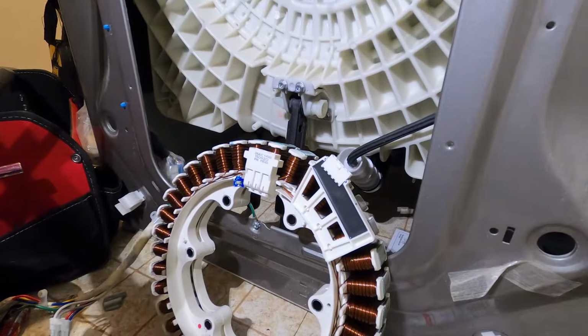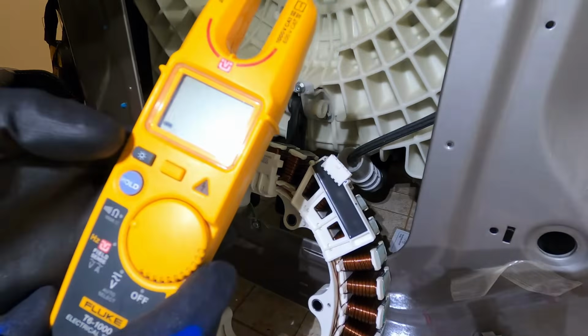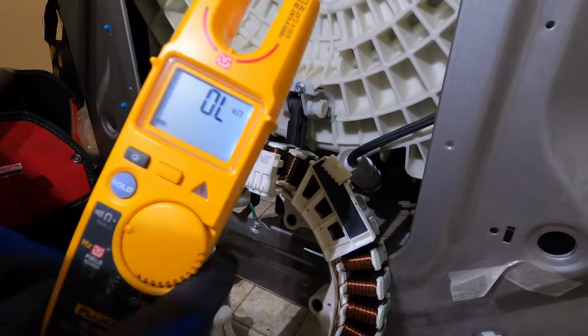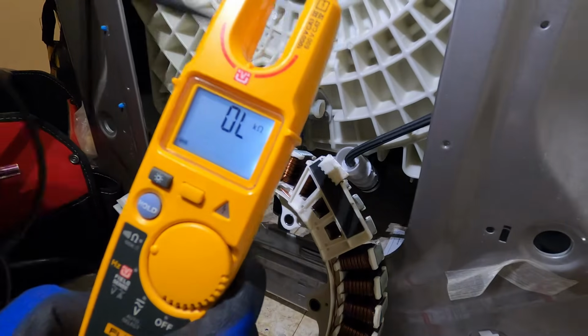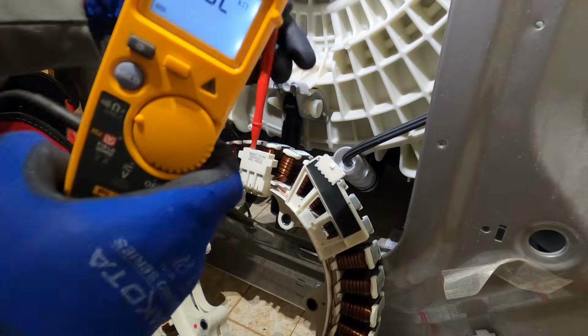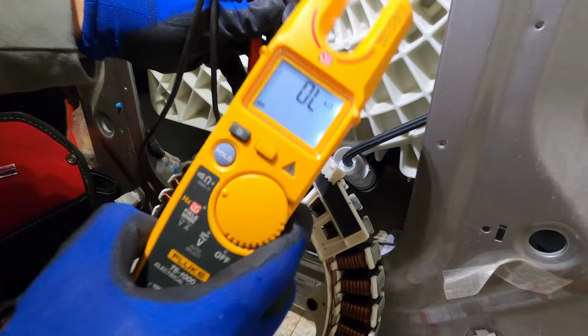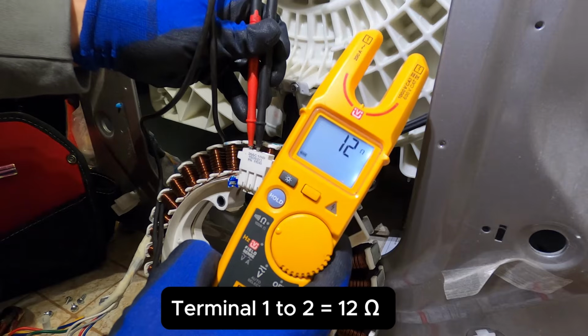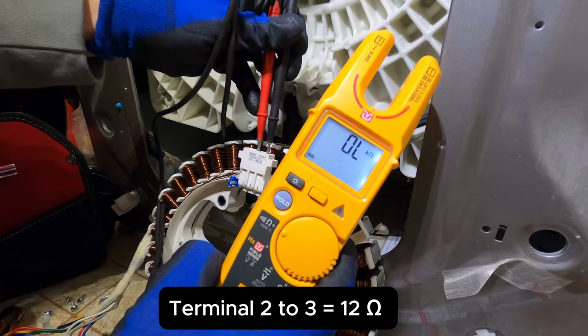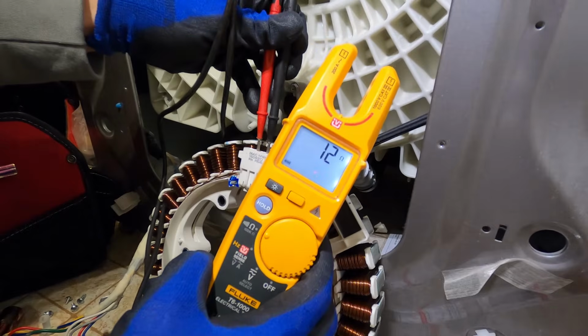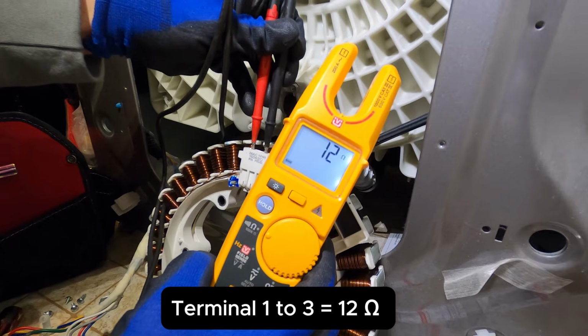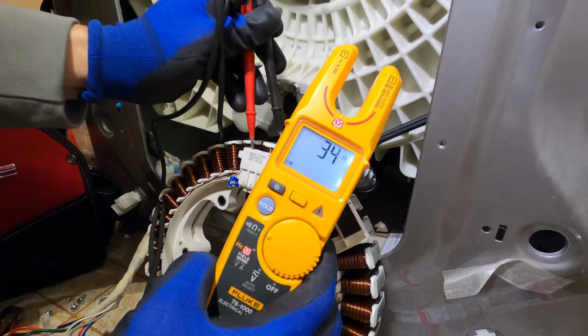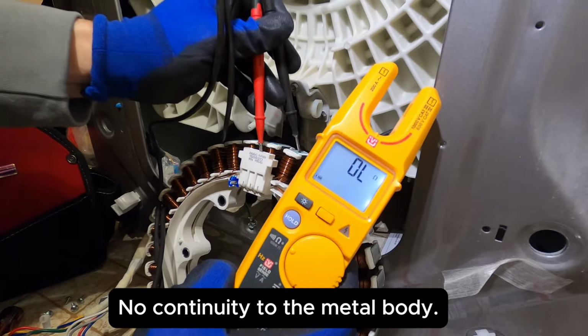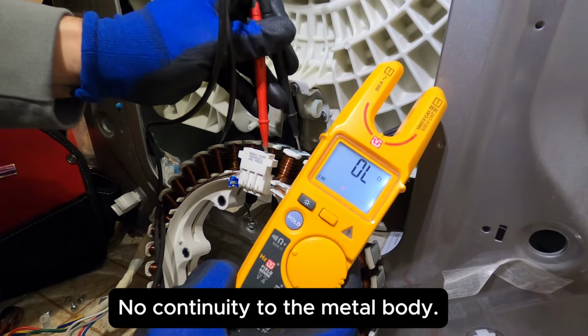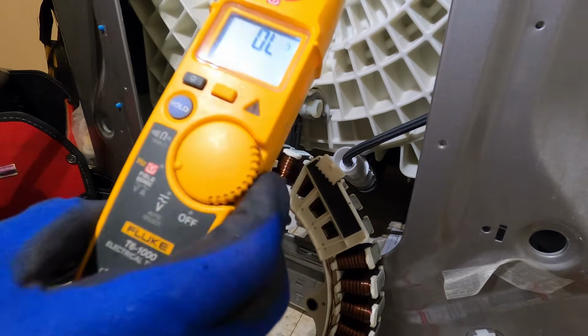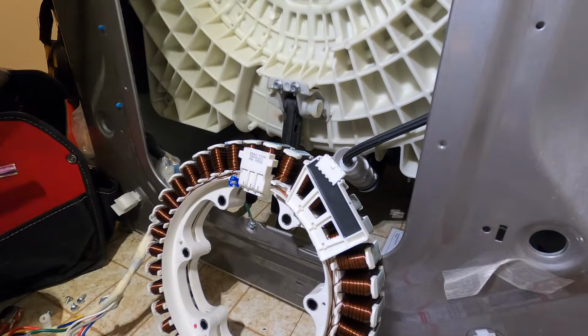Now, let's test the stator windings. This is a brushless motor and it has 3 similar windings. You need to use a multimeter to check the resistance of the windings. You should see identical ohm readings between each pair of terminals. By the way, the ohm reading might be slightly higher or lower than 12 ohms depending on the model.